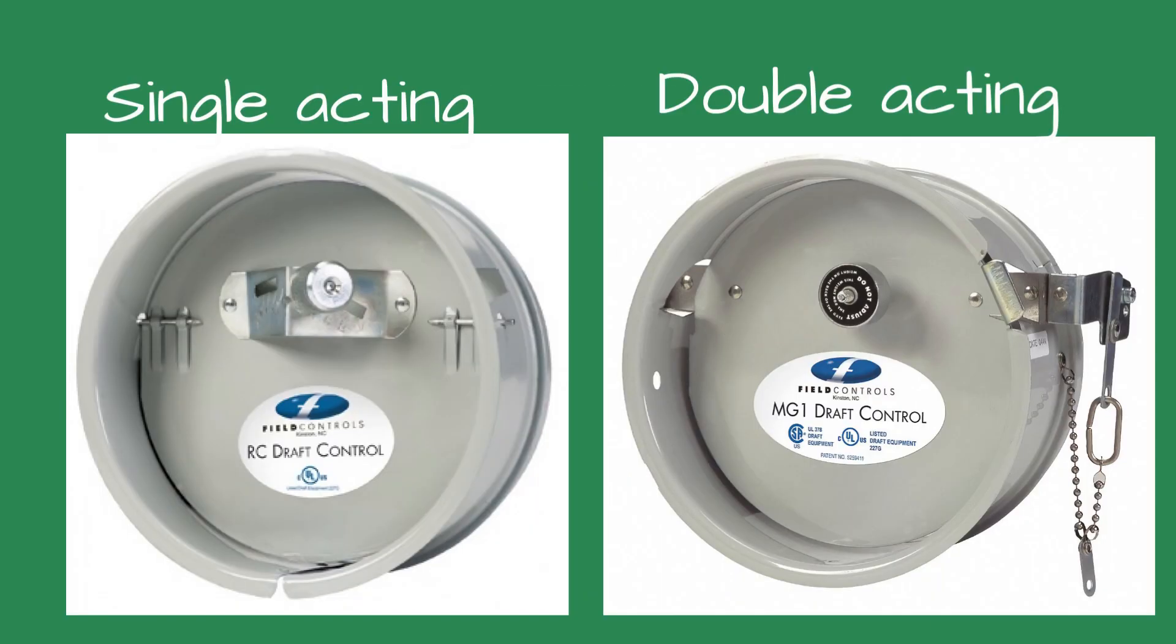When choosing a barometric damper, there are two types: single and double-acting. A single-acting damper has a stop that only allows the damper to swing one way. A double-acting one allows the damper to swing two ways. The single-acting damper will close if positive pressure exists inside the stack. The double-acting damper could allow spillage of the flue gases into the boiler room in the event of blocked flues or downdrafts.